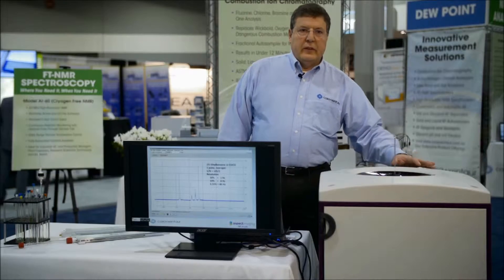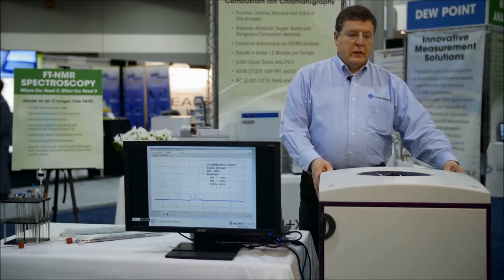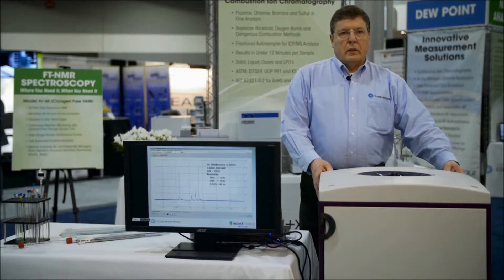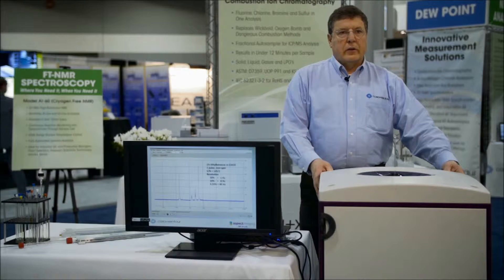The system consists entirely of a permanent magnet design requiring no cryogens as traditional high-field NMRs, and requires only a simple plug into the wall. It offers the ability to have the same performance in terms of sensitivity and resolution as traditional NMR spectrometers of much higher cost and field, but it is now able to go to the chemist, to the plant, or into the process without difficulty or obstacles.